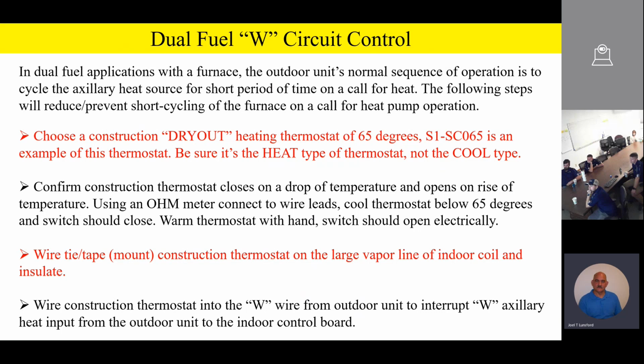Now, guys, this is important because if you don't utilize this, you can have some short cycling of the furnace. Now, it probably wouldn't hurt it in the short term, but in the long term, if you're only running the furnace for like 1 minute every time you have a call for heat on this heat pump, it's going to potentially rot the heat exchanger out, especially if you're on propane. So we don't recommend that you short cycle the furnaces, and this little construction thermostat will prevent that. The next thing you're going to do, you're going to wire that thermostat into the W wire from the outdoor unit to interrupt the auxiliary heat input from the outdoor unit to the indoor control board.